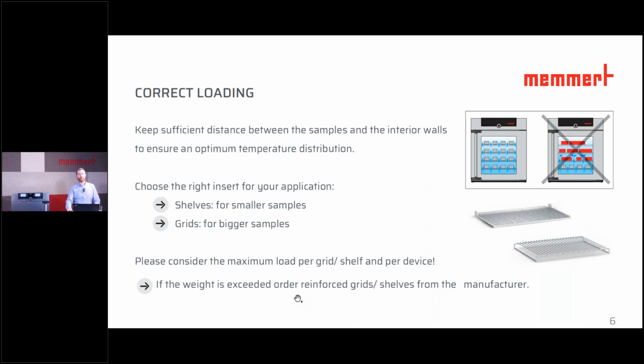Choosing the right insert for your application is also very important. Depending on the type of load, you should already decide on the right insert when buying the device. Perforated shelves offer a large contact surface and are therefore more suitable for smaller samples. Grids offer better air circulation and thus temperature and humidity distribution, and are in most cases more suitable for larger loads. Please always pay attention to the maximum load weight per grid or shelf. This is specified usually by the manufacturer.